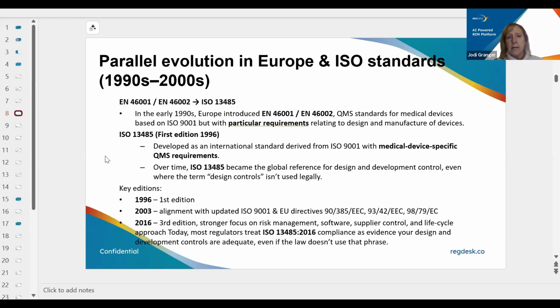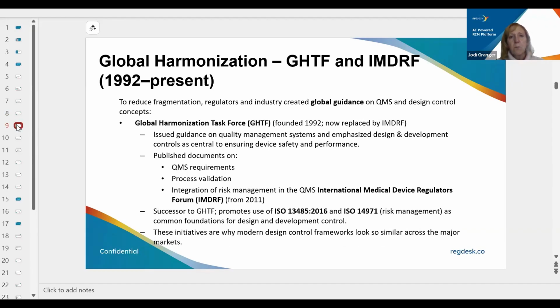And of course, that's been edited over time. The initial release was in 1996. That evolved in 2003, and then followed by the third edition, which is in 2016. This third edition really brought in a greater focus on risk management, how you control software, control of your suppliers, and how you manage your life cycle. So all of those updates in the 2016 have a direct impact on your design and development life cycle. So it's important to understand that even though the European legislation does not specifically state design control, the elements of the legislations and these standards are essentially the same thing. They just use different terminology.